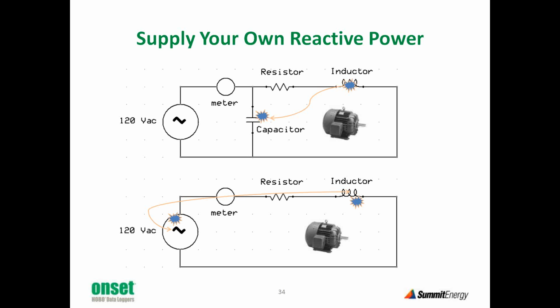So here's the good news. If you want to generate your own real power, you have to have a prime mover. If you want to generate your own reactive power, all you need is a capacitor. When we say that the utility is holding that energy for you every half cycle, what we really mean is they have capacitors that are holding it. If you put a capacitor on your side of the meter, you can't change physics. The reactive energy is still going to bounce between the inductor and the capacitor, but they're both inside your facility. The revenue meter never sees it.